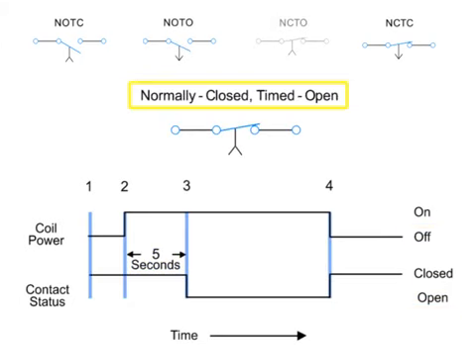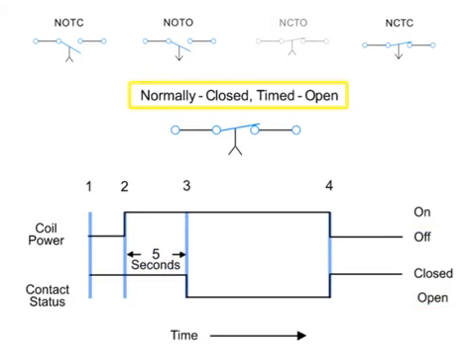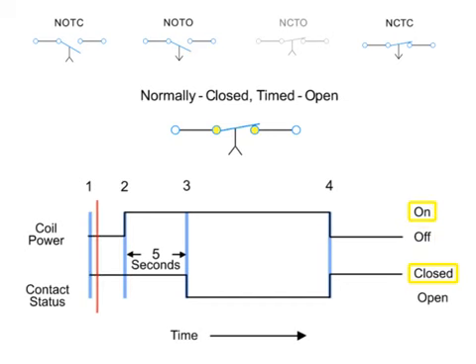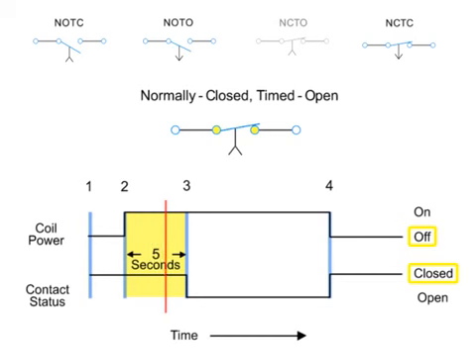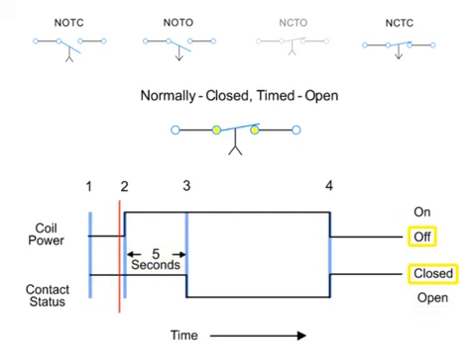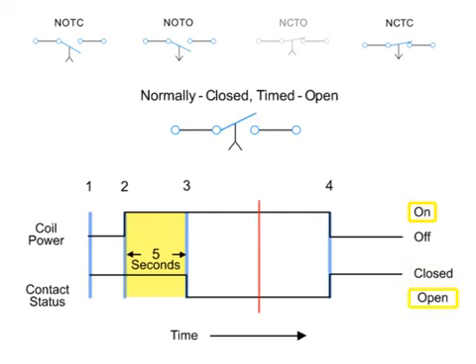Thus, the contacts close immediately when the coil is energized and open five seconds after the coil is de-energized. Next, we have the normally closed, timed open contact. This type of contact is normally closed when the coil is unpowered or de-energized. The contact is opened with the application of power to the relay coil, but only after the coil has been continuously powered for the specified amount of time — in this case, five seconds. Thus, the contacts open five seconds after the coil is energized and close immediately when the coil is de-energized.